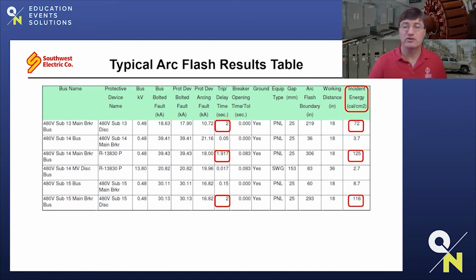Usually the first instinct is to get away from there as quickly as possible. So they allow for no more than 2 seconds for someone to get out of that area. And that's why it's set at 2 seconds. What this tells me is that at these buses, the protective settings are insufficient to detect and clear an arc flash event should it occur. It maxed out at the 2 second level, and that's what allowed all that incident energy to accumulate, as we saw earlier in the previous slide.